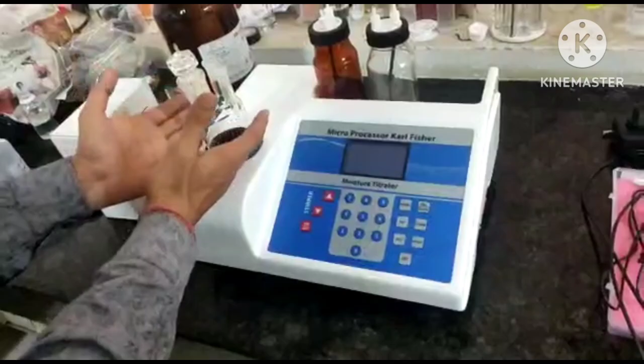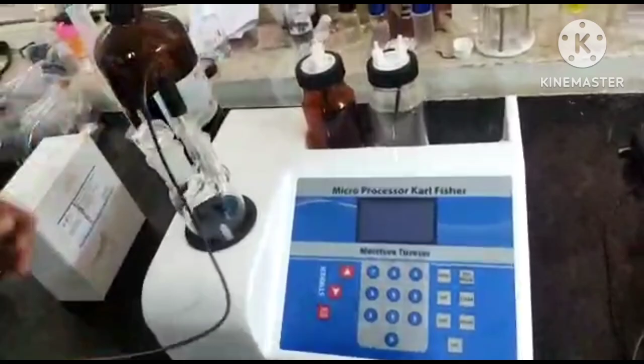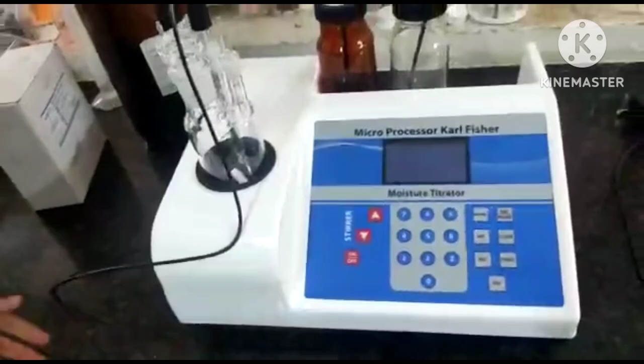Thereafter we have to put our titration vessel. This is what we call the titration vessel. We have to put the titration vessel here, and we have to put a magnetic bead inside this one, like that. Thereafter we have to connect our electrode. So we have to put the electrode here, and we have to connect it on this position. So the connections on this side are the electrode, the on-off switch, and the power adapter connector. So these are the three connectors on the left. So we have connected on the electrode side. So these are the connections for the electrode.